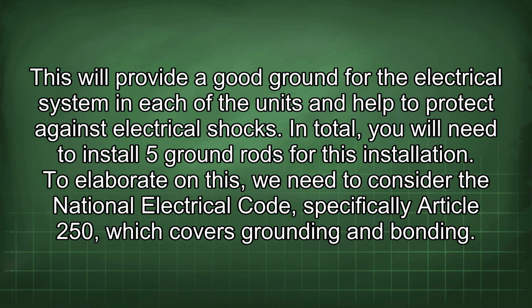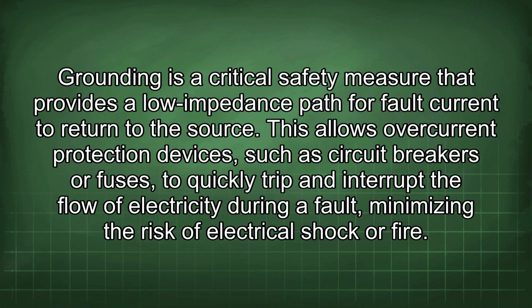To elaborate on this, we need to consider the National Electrical Code, specifically Article 250, which covers grounding and bonding. Grounding is a critical safety measure that provides a low impedance path for fault current to return to the source. This allows overcurrent protection devices, such as circuit breakers or fuses, to quickly trip and interrupt the flow of electricity during a fault, minimizing the risk of electrical shock or fire.